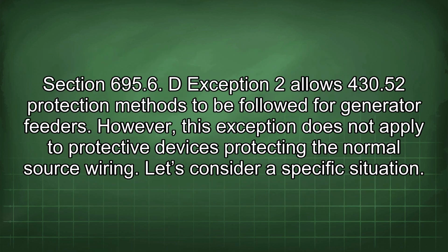Section 695.6, exception 2 allows 430.52 protection methods to be followed for generator feeders. However, this exception does not apply to protective devices protecting the normal source wiring.